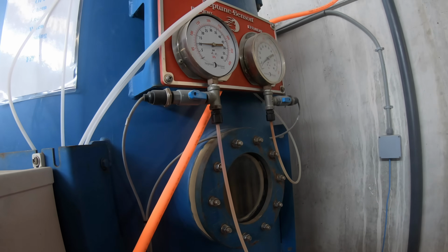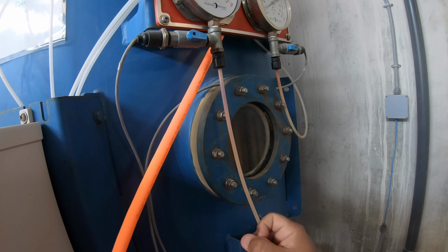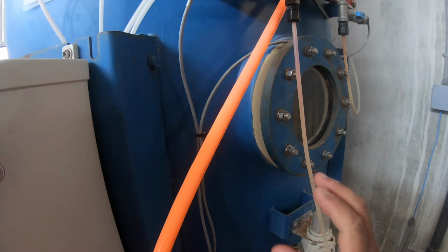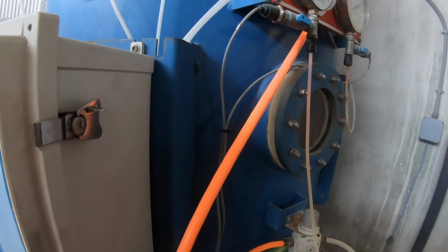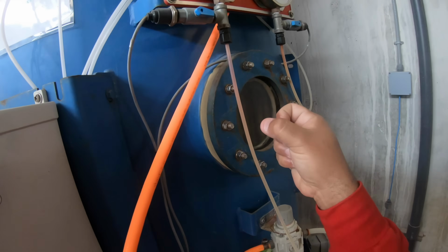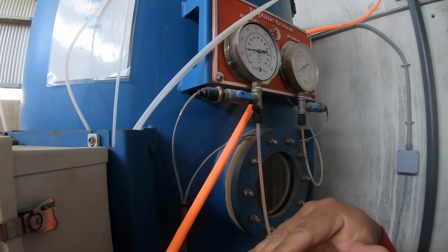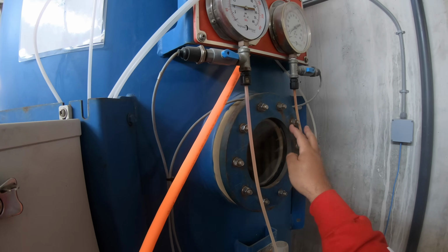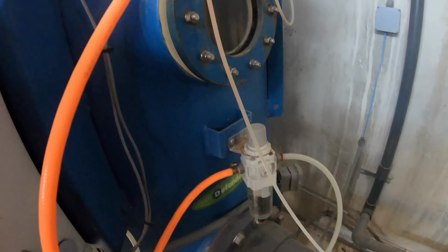So that means that the media right now is a little dirty. It's got a lot of particulate inside of it. Now, the thing about a regenerative is I'm gonna knock everything off, I'm gonna restart it, and a lot of the heavy stuff is gonna stay at the bottom while the media sticks back to the tube, okay? And then my differential is gonna be a lot less. Should be almost even. Right now, this media is a little older now that we've been sitting on it, so it's probably gonna be at around the 3 or 4 differential, which is okay, that's fine.